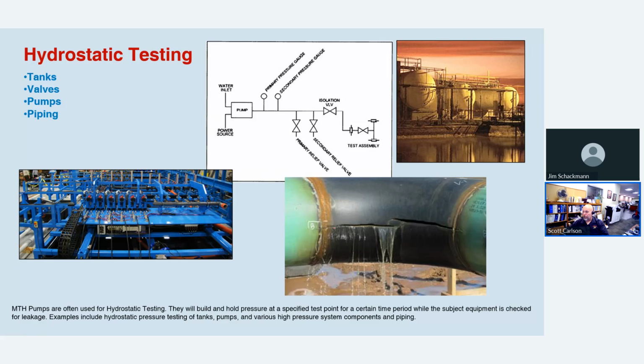and you can do all your inspections to make sure that there are no leaks coming from anywhere because of bad welding or seals or anything else. So it's a good way to hydrostatic test any piece of equipment.